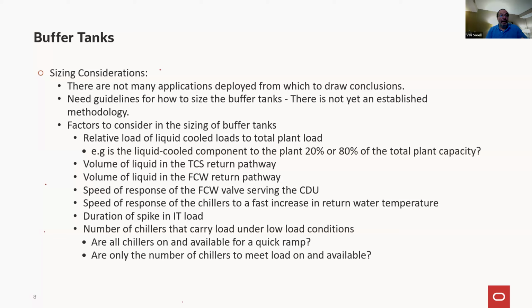So are they all on and available? Are they ready, like, at idle? Can you keep them all at idle, or do they drop below a certain load? You do have to turn off chillers if there's no load to them. So you have to balance the energy efficiency at idle or at very low load for that chiller. Is it worth it for me to address that risk by having as many chillers as I can keep on at that time? Do I want to keep them on and at idle so that they are ready for this kind of spike? And again, the type of spikes, the number of spikes really plays into that.